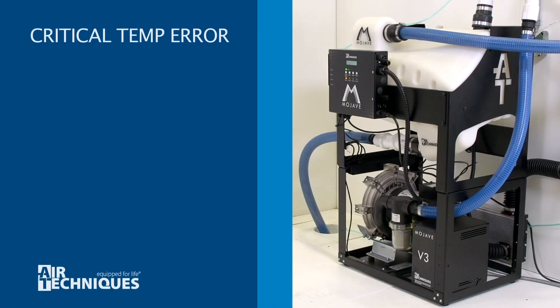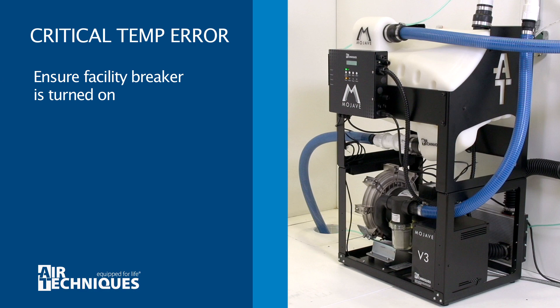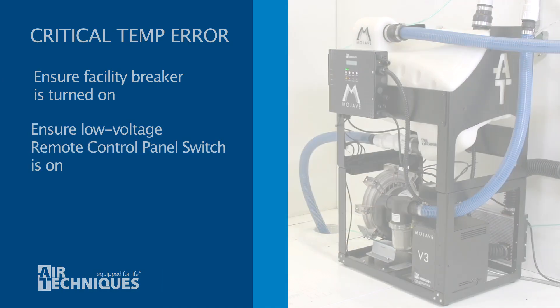If you have no suction and the pump doesn't run, ensure that the MMC is plugged in and the circuit breakers are not tripped. Then check that the circuit breaker on the power module is in the on position. Be sure that the facility breaker is switched on as well as the low voltage remote control panel switch.